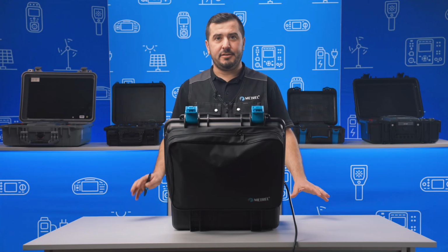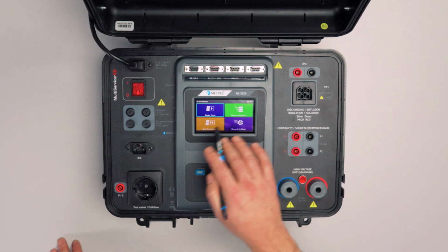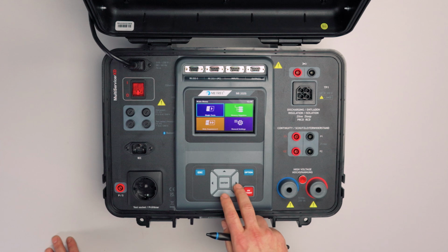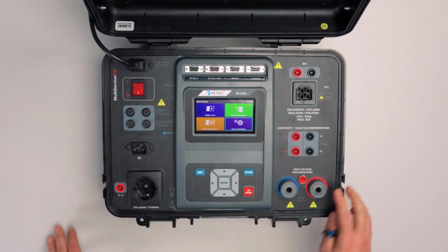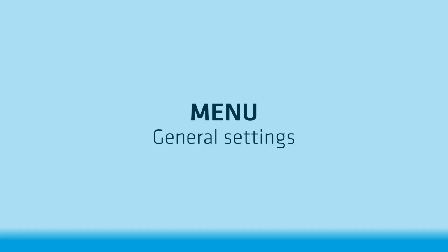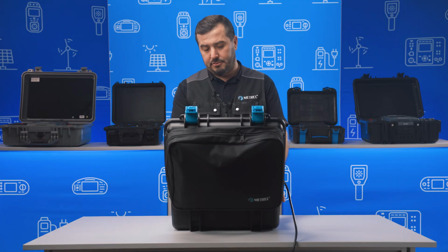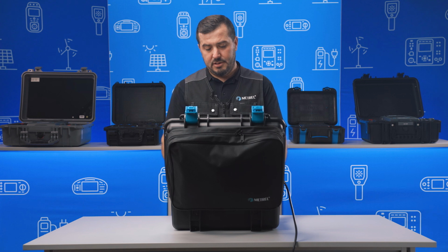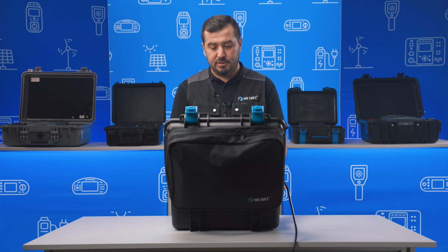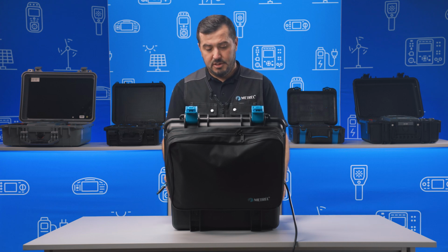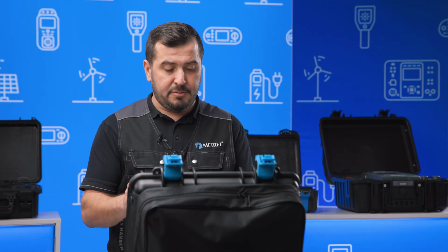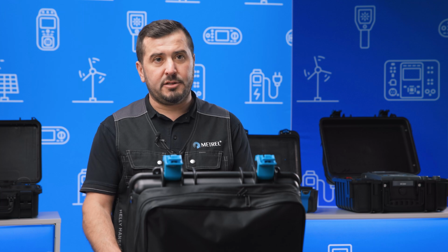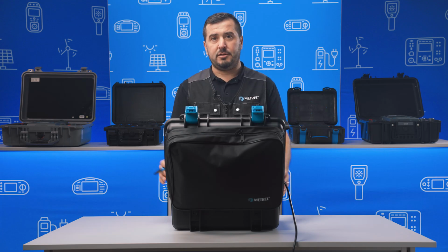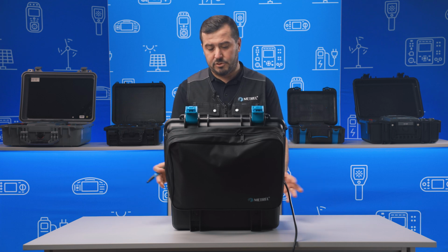Okay, let's now check the instrument's menu. As you can see, there are 4 groups in the main menu, and we will first focus on the general settings. Inside the general settings, we can select between different language options. Then, of course, we can adjust date and time. Make sure that this is adjusted before starting to use the instrument. Why is this important? Because the time and date stamp will be assigned to every performed measurement, and for the traceability of test results, this is of course very important.